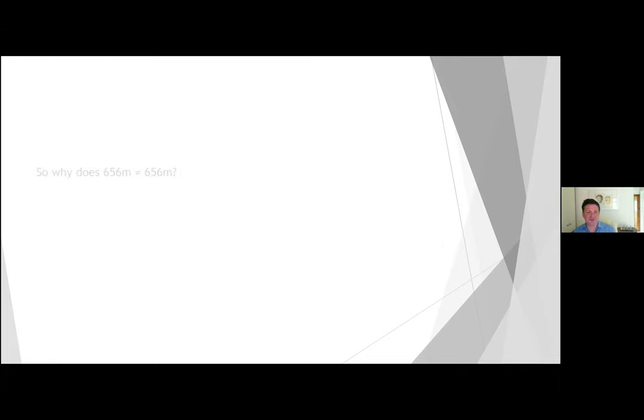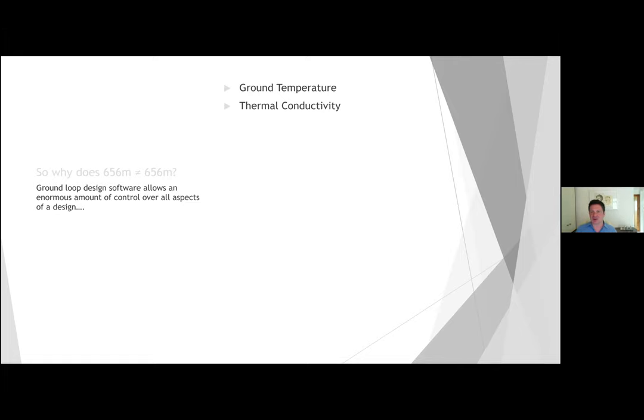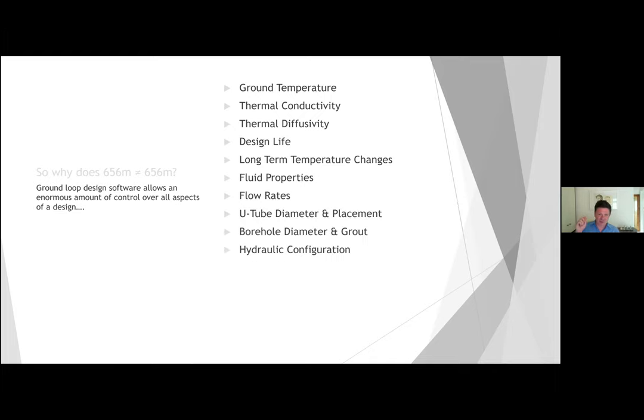Why does 656 metres not equal 656 metres? Well, the ground loop design software allows us an enormous amount of control over all aspects of the design — not just the obvious ones like ground temperature and thermal conductivity that you have control over with the MCS tables. There's a huge list, and most of these are not just a single parameter but actually a number of parameters. For example, we can adjust the thermal diffusivity — analogous to conductivity — which is how quickly temperature differences propagate throughout the ground, or put another way, how much interference you get between boreholes. It's a really core parameter in ground loop design that you simply do not have control over in the MCS tables.